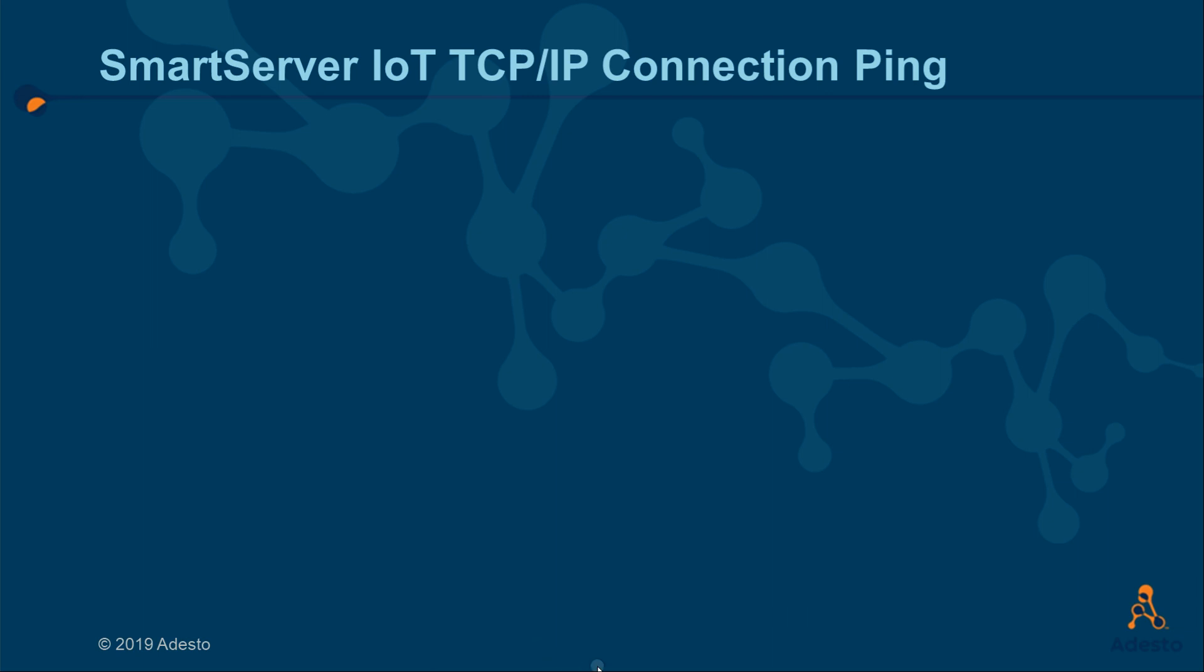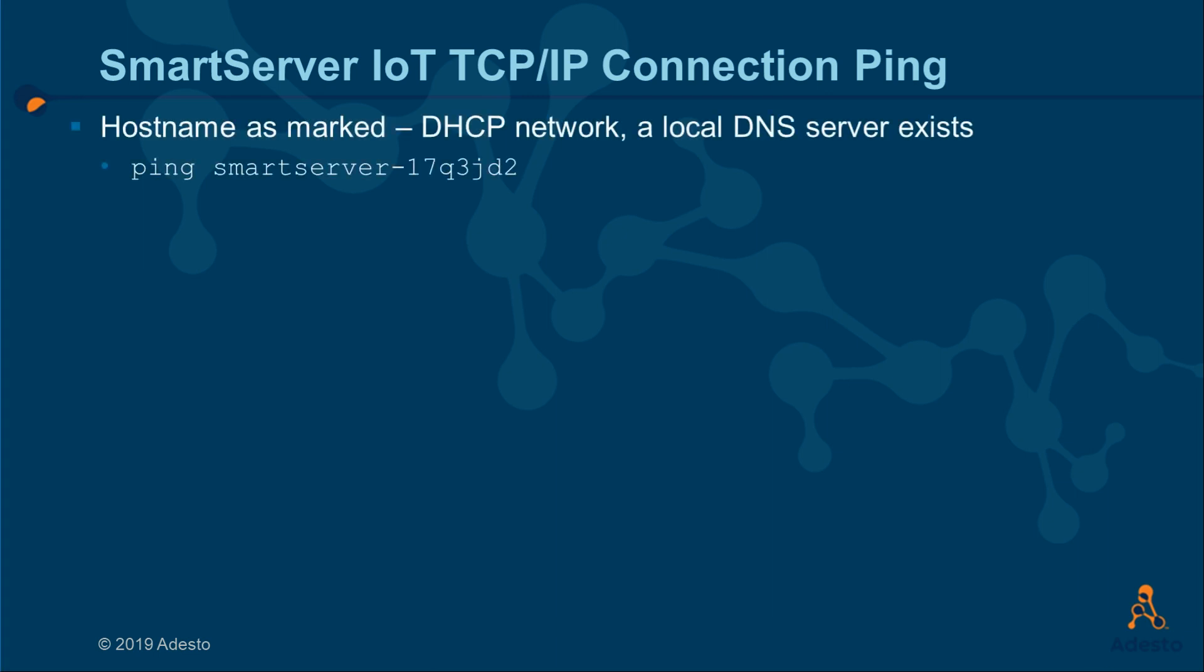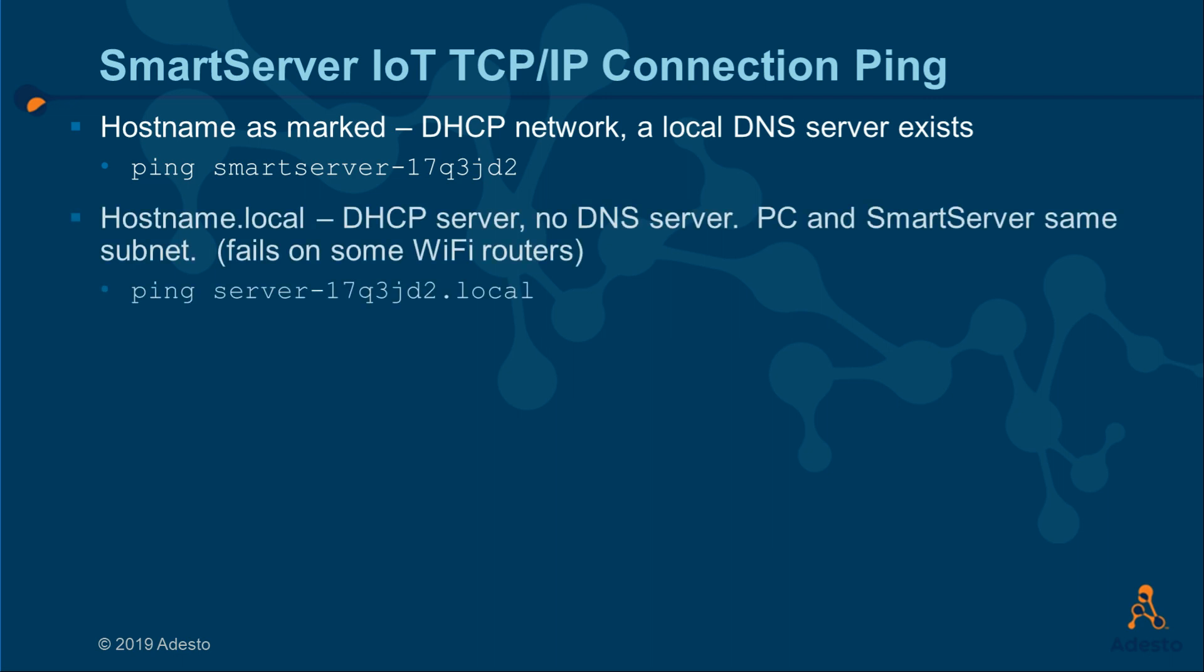As a network connected device, the Smart Server IoT's TCP IP address is essential to know. Let's enumerate the different networks that might exist. First, in a network with DHCP and DNS enabled, you can reach the Smart Server directly with its host name. If there is no DNS server available, but DHCP is enabled, you may need to engage mDNS and add .local to the host name to reach the Smart Server.